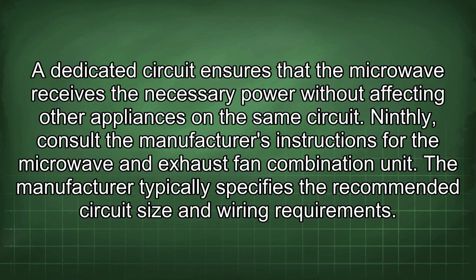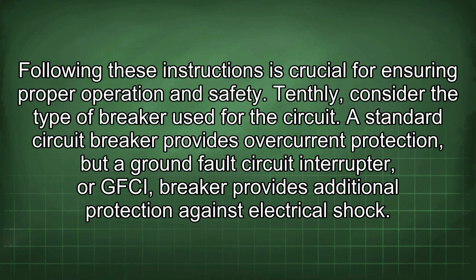Ninthly, consult the manufacturer's instructions for the microwave and exhaust fan combination unit. The manufacturer typically specifies the recommended circuit size and wiring requirements. Following these instructions is crucial for ensuring proper operation and safety. Tenthly, consider the type of breaker used for the circuit. A standard circuit breaker provides overcurrent protection, but a ground fault circuit interrupter, or GFCI, breaker provides additional protection against electrical shock.